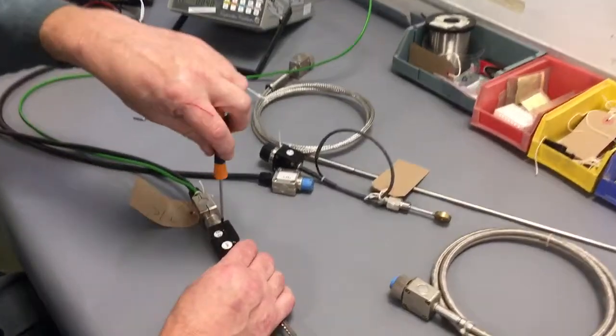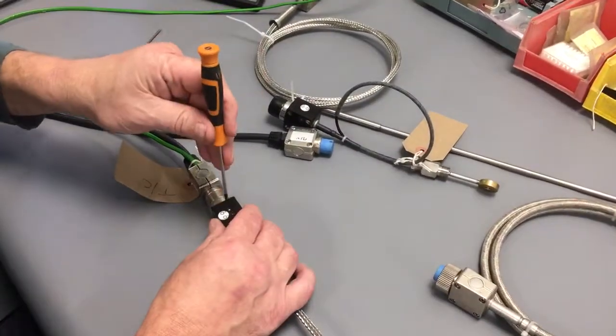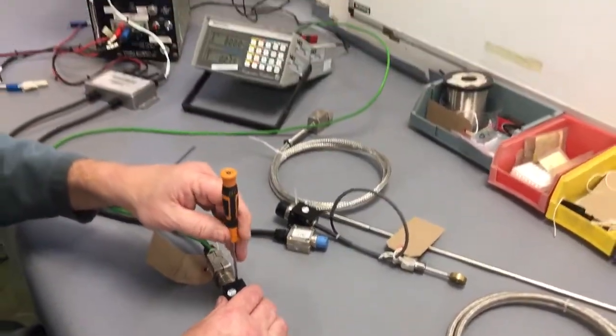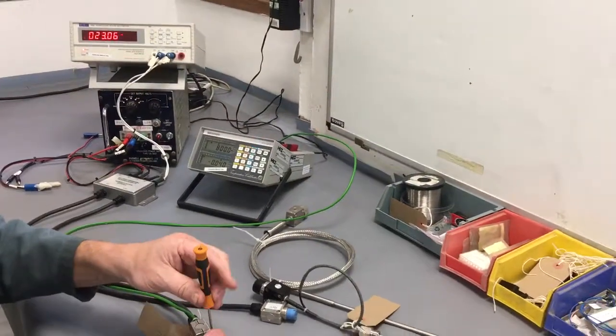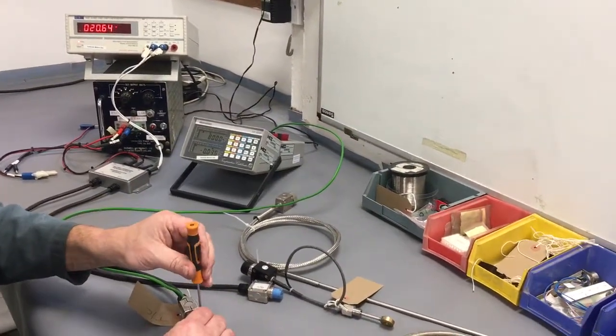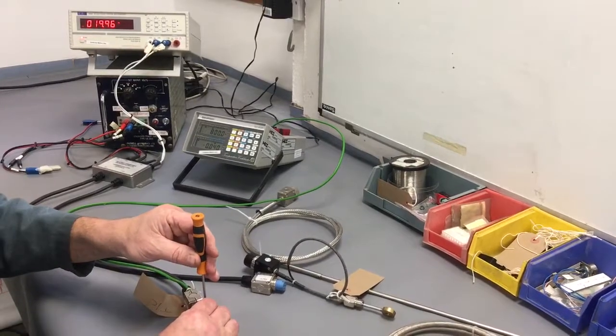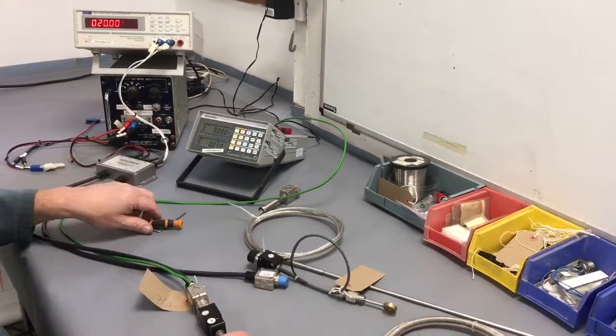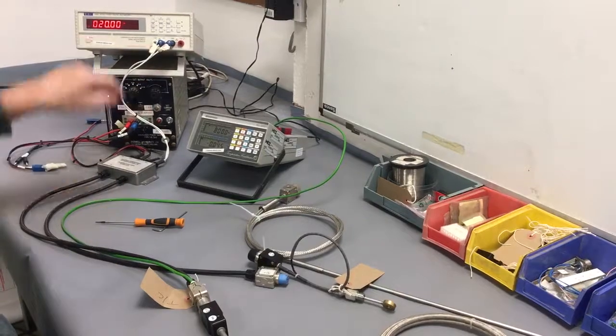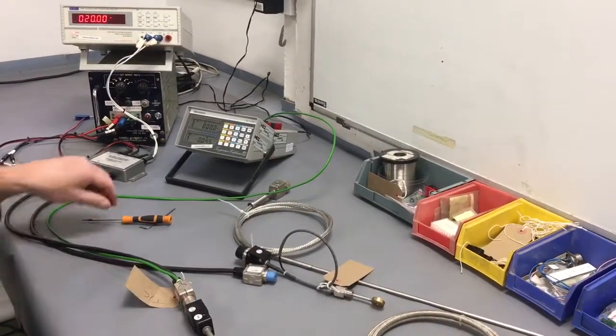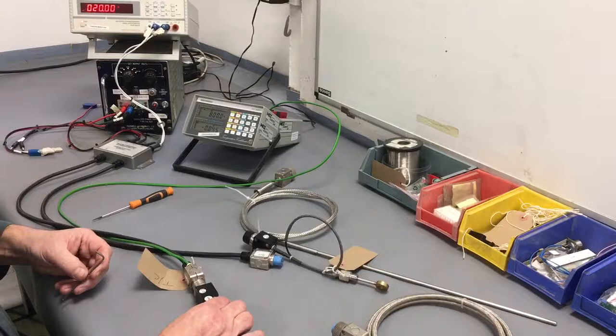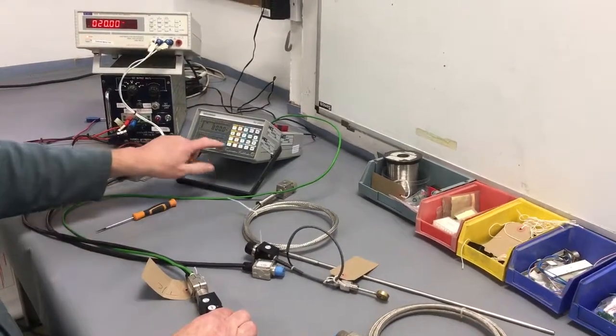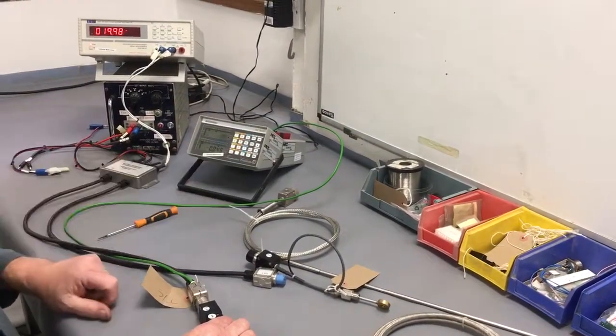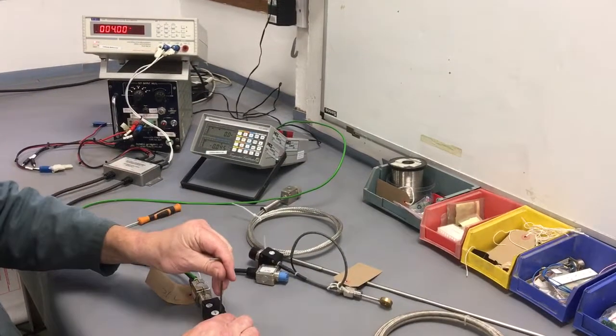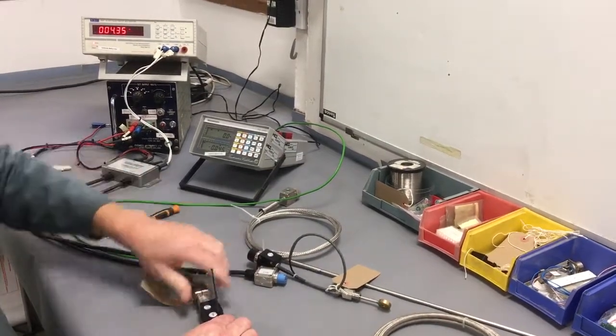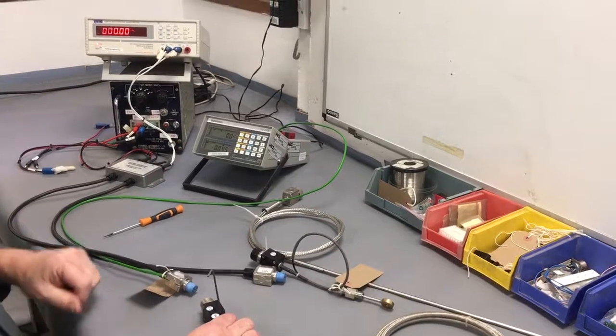So we then adjust the span pot. As you can see, very easy. There we go, 800 degrees C, 20 milliamps. The sensor is in the diagnostic position, so we go back to 0, 4 milliamps, close the circuit, calibrated, job done.